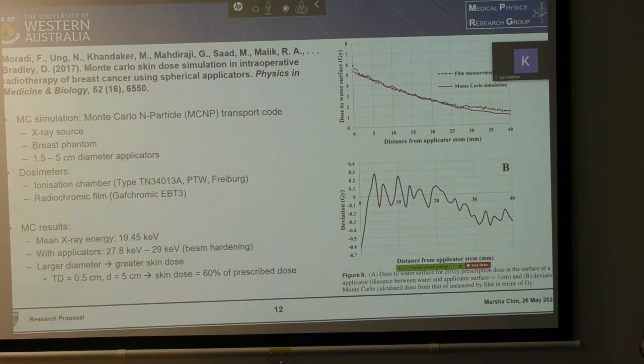This is one of the key articles, Moradi et al. So they simulated the X-ray source as well as the breast phantom on the MCNP transport code. They used 1.5 to 5 centimetre applicators. They also performed physical measurements using ionisation chambers and radiochromic film. So they found the mean X-ray energy to be around 19.45. The ideal one was 20 keV, so that's pretty close. However, with applicators sitting on the X-ray probe, the X-ray energy was higher due to beam hardening.